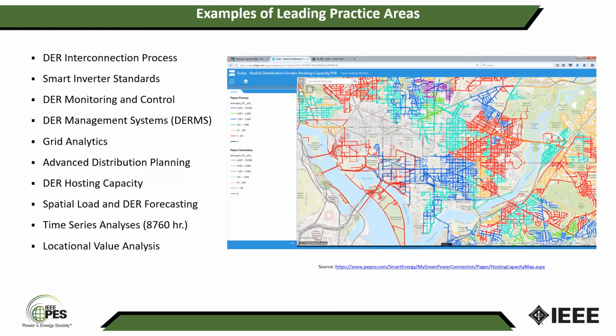One interesting area is what we call hosting capacity: analyzing the grid to understand the amount of DER that can be interconnected to the distribution grid, and using that as a guideline for developers and customers to interconnect their systems. In this specific case, the areas in red are areas of a distribution system where there is barely enough capacity in the grid to interconnect distributed resources without causing impacts. As a developer, I'd rather not try to interconnect systems in those areas, because very likely it's going to trigger an improvement project that developers will have to pay for.